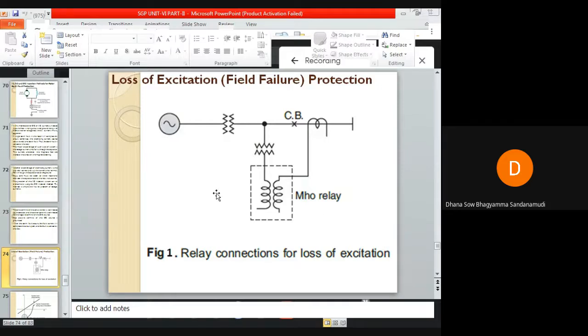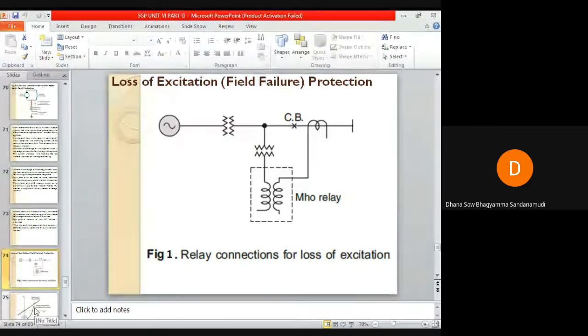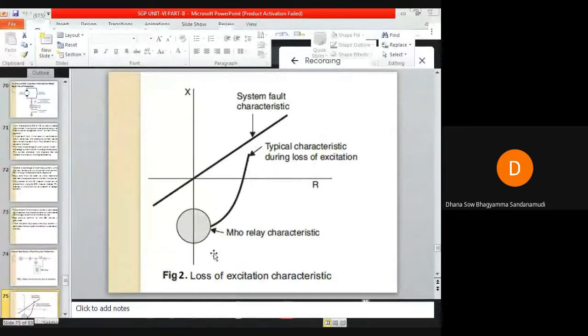In this image you can see the offset Mho relay. This is our generator, this is our circuit breaker, this is the CT which is measuring the current in this line, and this is the RX diagram. This shows the characteristics of this offset Mho relay.